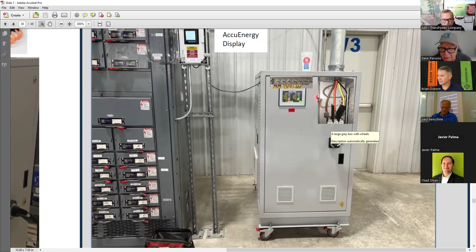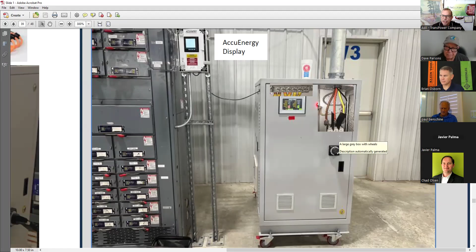Bill, is there a spec on the distance between them? Yeah, that is in their code book. Dave, I believe for 480 volts, minimum clearance is, I think, 1 inch. We provide more than 1 inch because the breaker provides the distance that Dave brought up. But what happens is they are providing that 1 inch distance, thinking that the wire is going to go inside the breaker. There is no exposed metal outside the breaker. But the moment you bring the connection outside the breaker, you have to be cautious. That was an extremely good question.